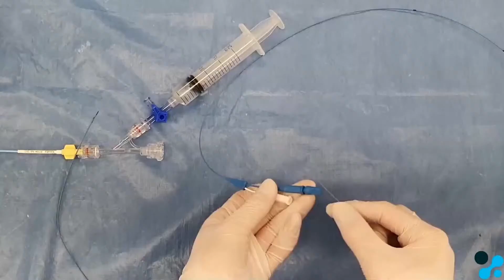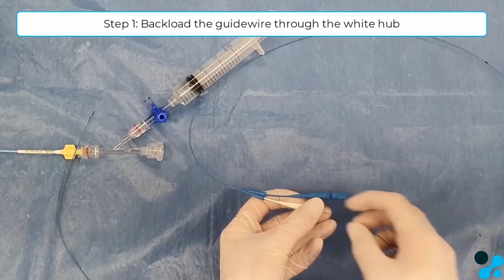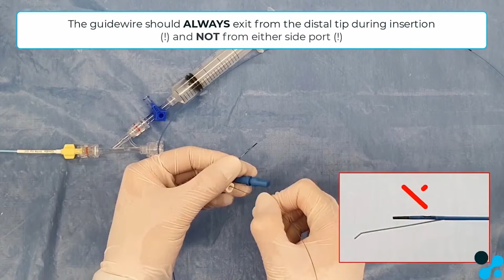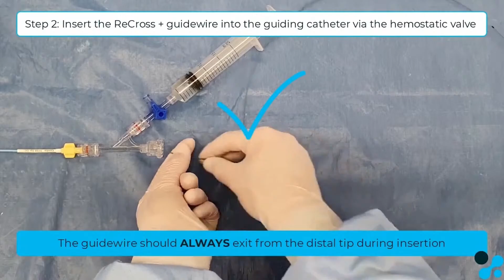The Recross can be inserted together with the guide wire. Backload the guide wire from the white tip hub. The guide wire should always exit the tip. So not exit the proximal exit port, it should always come over the tip. Insert the Recross plus the guide wire through the hemostatic valve into the guiding catheter.